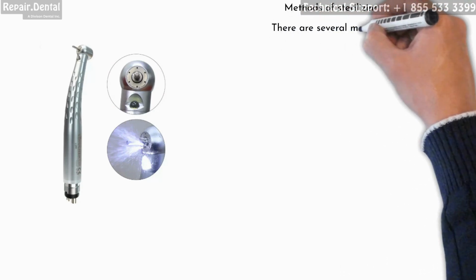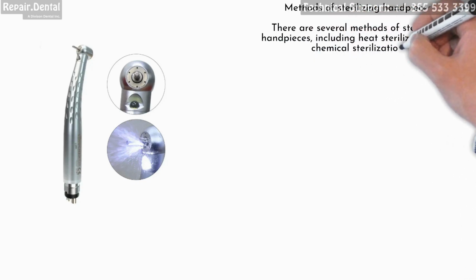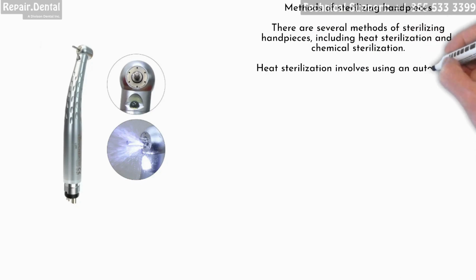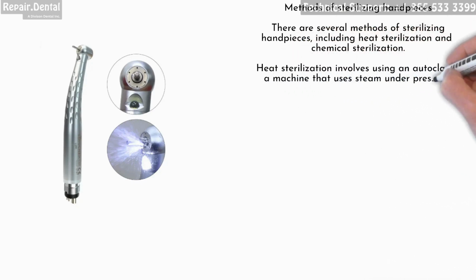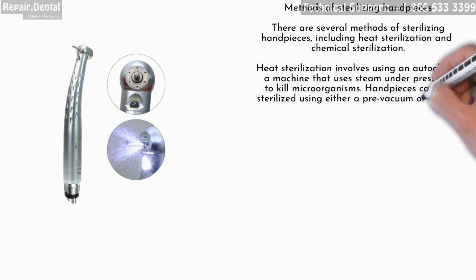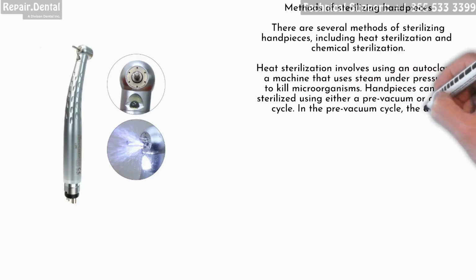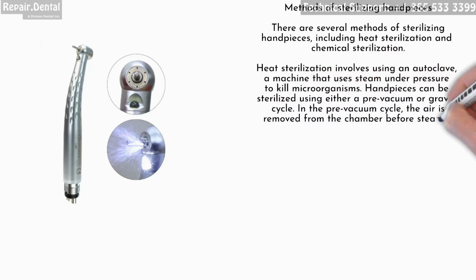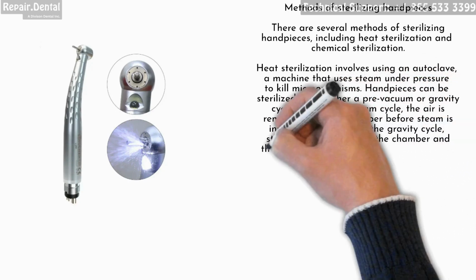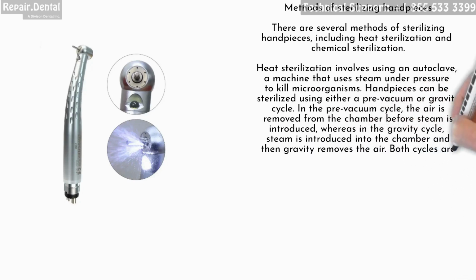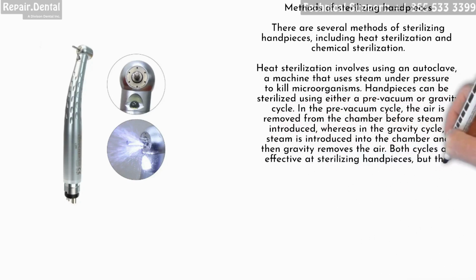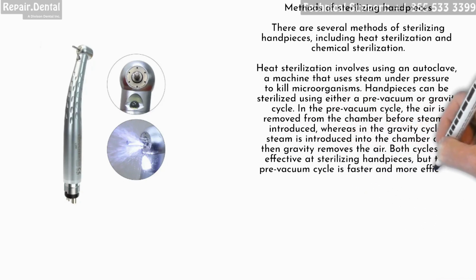Methods of sterilizing handpieces. There are several methods of sterilizing handpieces, including heat sterilization and chemical sterilization. Heat sterilization involves using an autoclave, a machine that uses steam under pressure to kill microorganisms. Handpieces can be sterilized using either a pre-vacuum or gravity cycle. In the pre-vacuum cycle, the air is removed from the chamber before steam is introduced, whereas in the gravity cycle, steam is introduced into the chamber and then gravity removes the air. Both cycles are effective at sterilizing handpieces, but the pre-vacuum cycle is faster and more efficient.